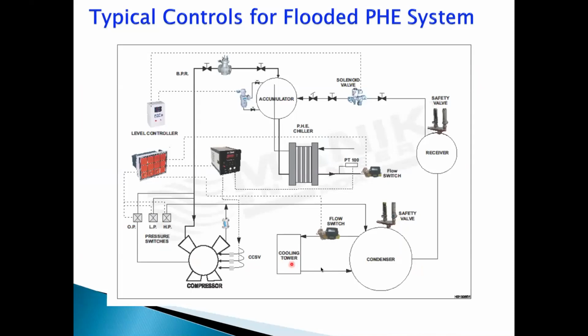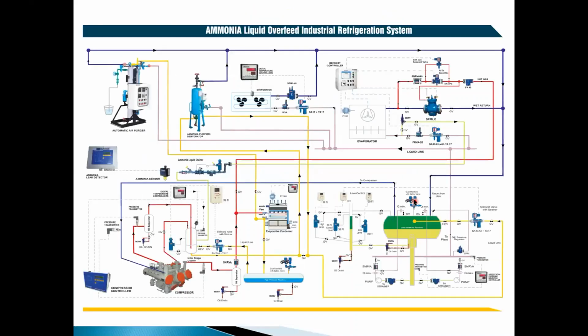This is a typical schematic. As I was telling you, you have a PHE or plate type or different types of chillers with an accumulator, where you provide a level control and liquid feeding through the solenoid valve. To avoid freezing of these chillers, you provide a back pressure regulating valve and other controls; the compressor capacity control and other things can make your plant fully automatic.